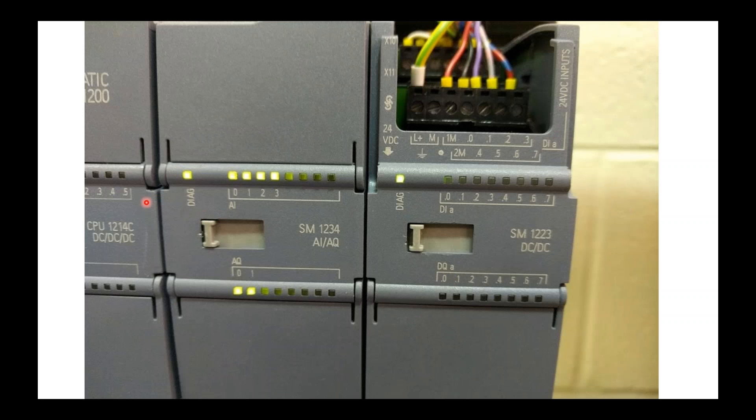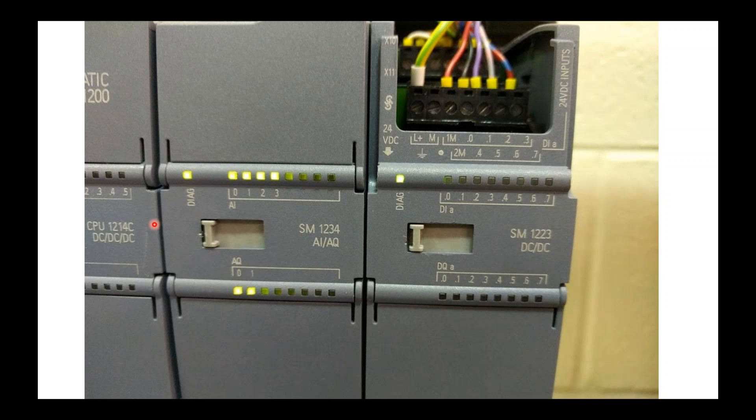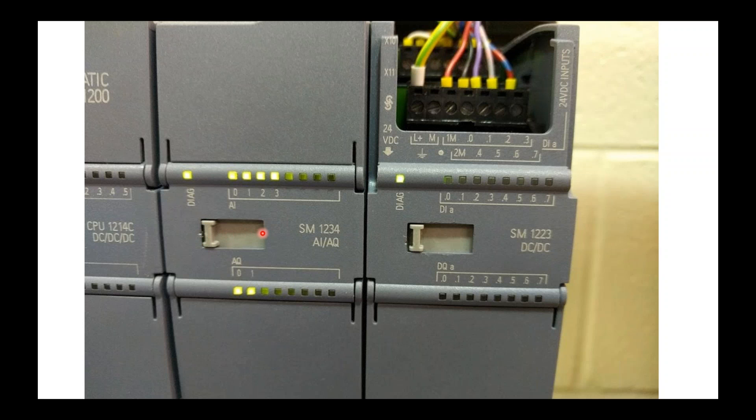You'll see if you open this up, there's going to be like a little small gray tab here that I have to remove. And that's where my input cards sync together. In some processors, it's called a back plane. In this case, it's a front plane. Everything is connected via the front. When you buy these, this little bracket will be pushed over to the right. And I would need to push in and then drag over to the left.